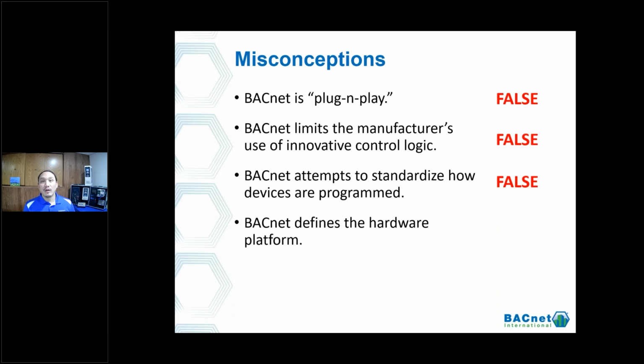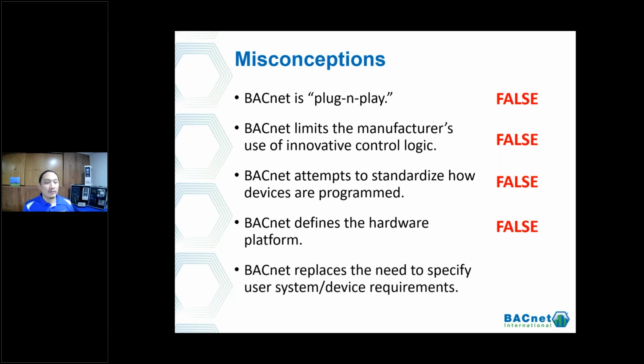Another misconception: BACnet defines the hardware platform. It doesn't. If you're implementing BACnet MSTP, all you need is a serial chip. It doesn't say a specific one, it just says that's what you need to implement. If you implement BACnet IP, same thing. It doesn't tell you what processor to use, what MAC-PHY to use, or what connector to use. There's a lot of variety out there, and it gives you the capability to choose what works best for you, especially if you're a device manufacturer.